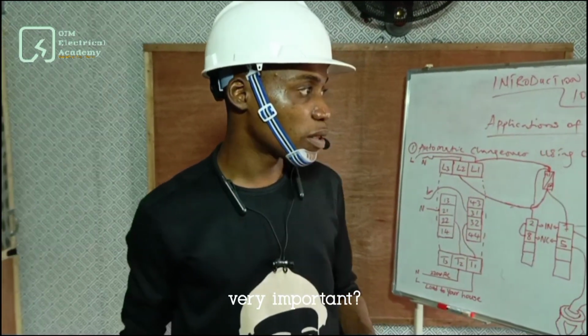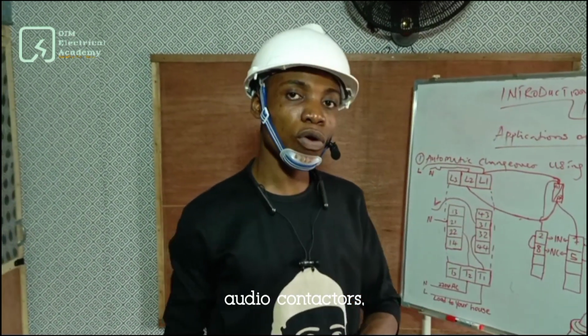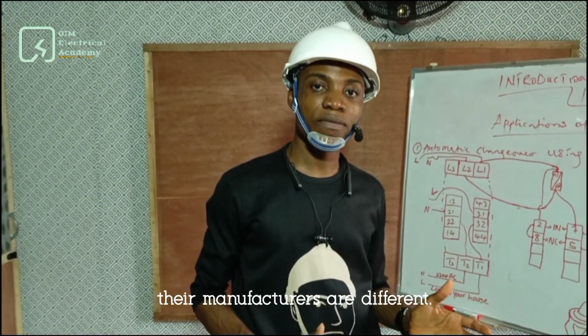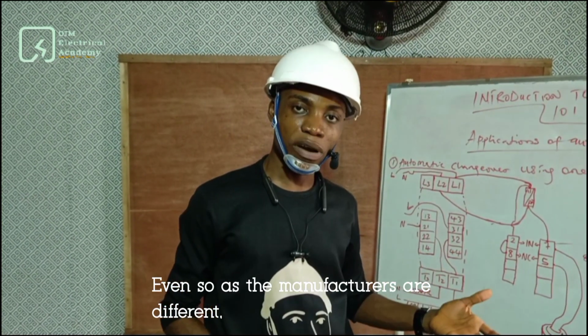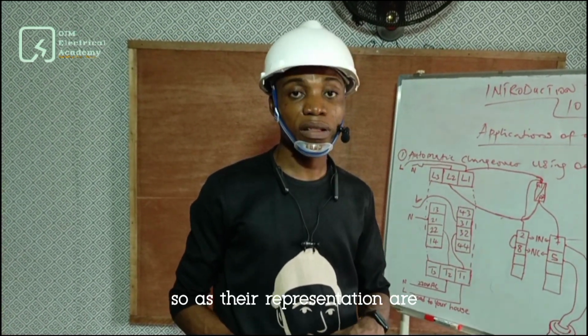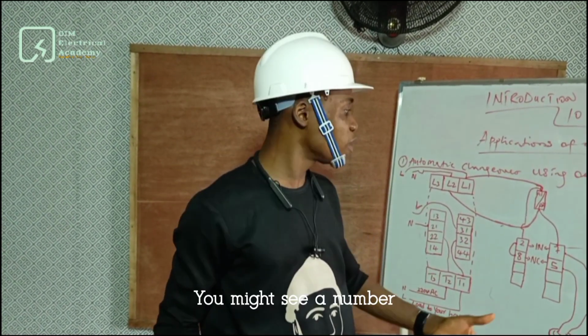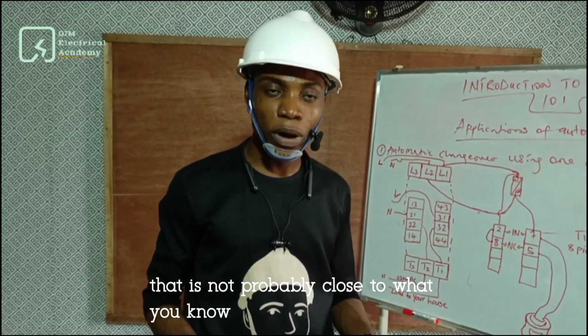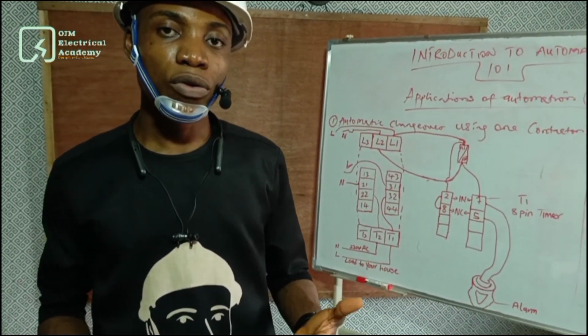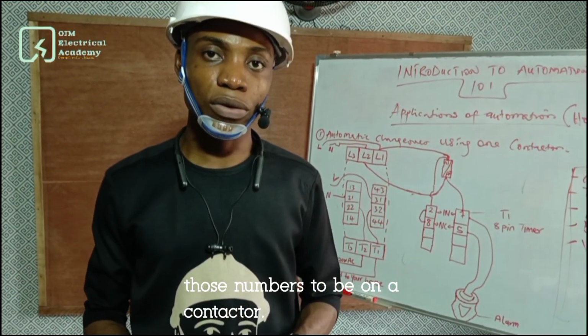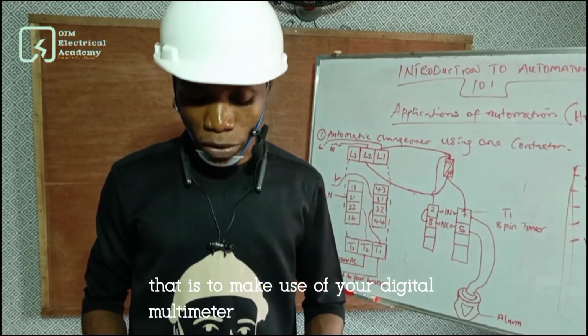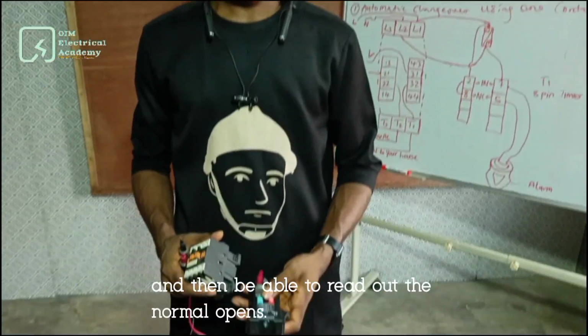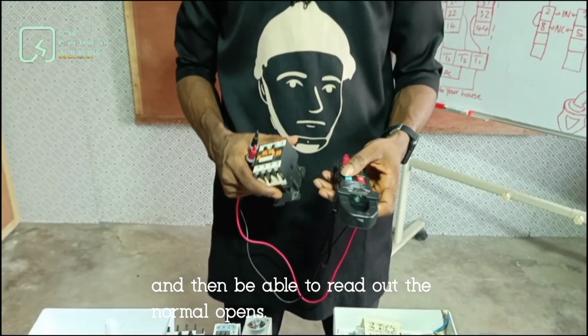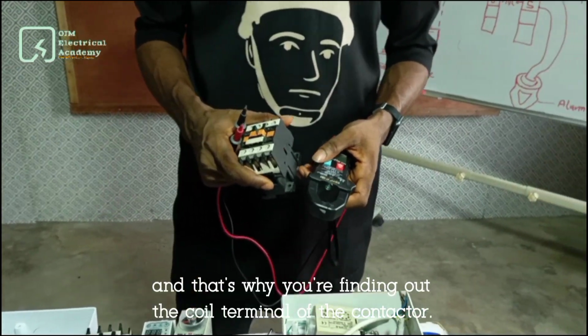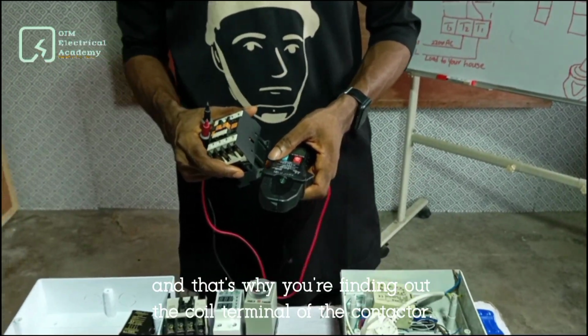Why is it very important? There are some contactors where the manufacturers are different, and since the manufacturers are different, their representations are also different. You might see a number that is not close to what you know those numbers to be on a contactor. Another way to identify that is to make use of your digital multimeter and read out the normally opens and normally closed, as well as finding out the coil terminal of the contactor.